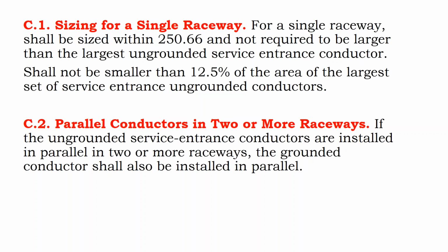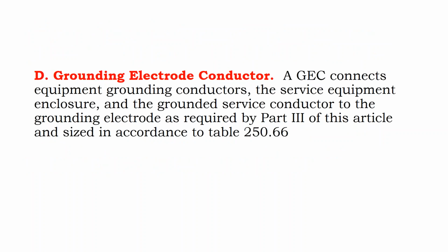The problem is when you're doing parallel runs, you can't just have one run for your grounded conductor that might be a smaller size and then leave it out of the other run. You need to run your grounded conductors in parallel as well. We already defined the grounding electrode conductor.